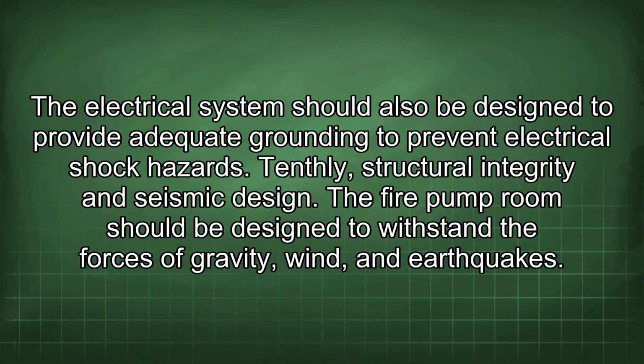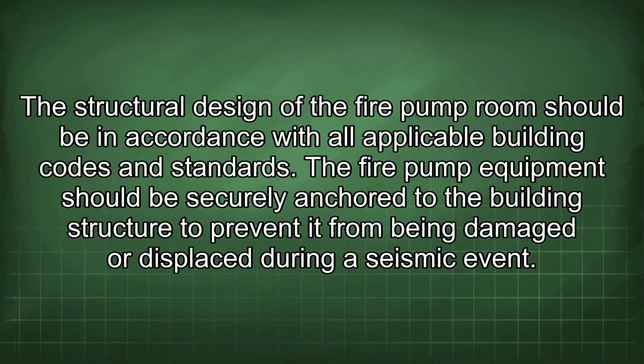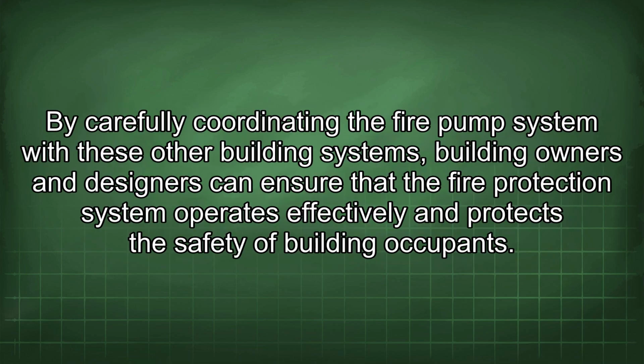Tenthly, structural integrity and seismic design. The fire pump room should be designed to withstand the forces of gravity, wind, and earthquakes. The structural design of the fire pump room should be in accordance with all applicable building codes and standards. Fire pump equipment should be securely anchored to the building structure to prevent it from being damaged or displaced during a seismic event. By carefully coordinating the fire pump system with these other building systems, building owners and designers can ensure that the fire protection system operates effectively and protects the safety of building occupants.